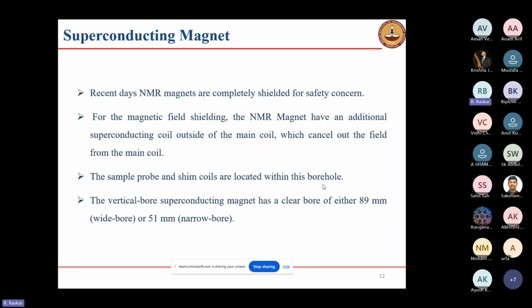Recently, all the magnets are completely shielded, so that's why we are safe. The NMR sample probe and shim coils are located within this borehole. As I already told, two kinds of bores are there. One is the wide bore, which is 89 mm, and the other is the standard bore, which is 51 mm. The wide bore is suitable for solid state and imaging probes. The narrow bore is suitable for regular solution experiments.